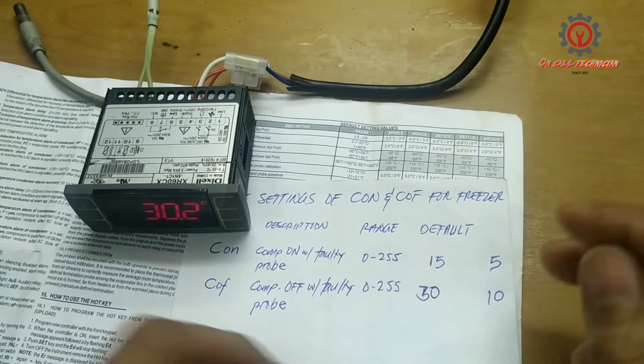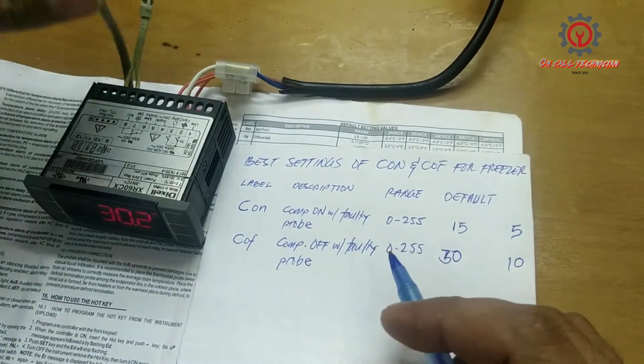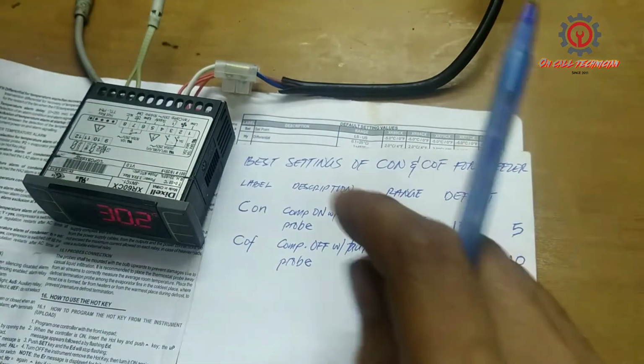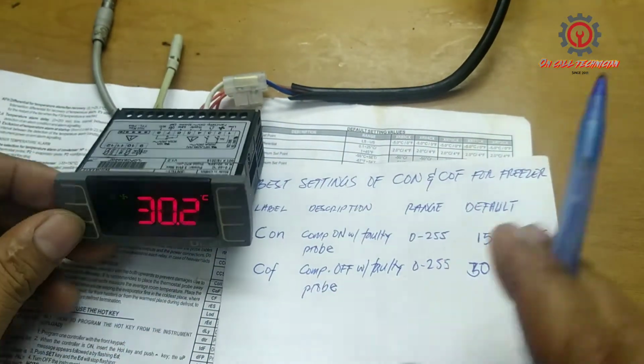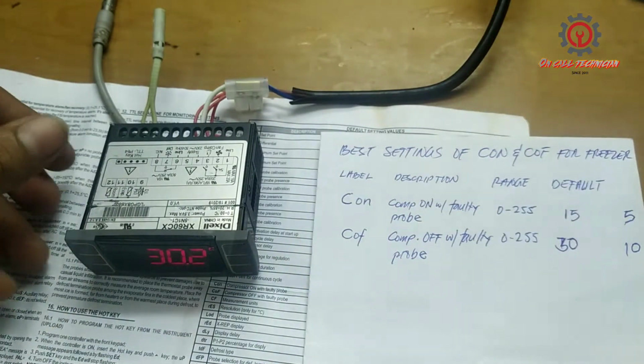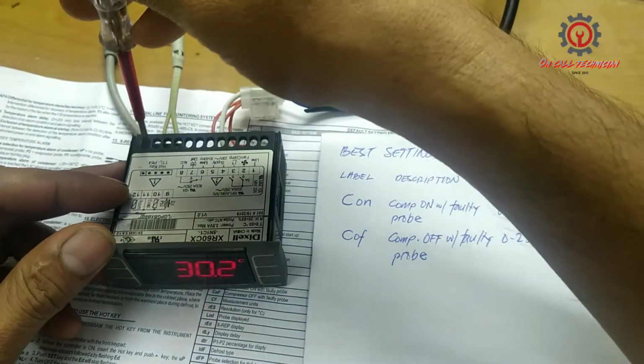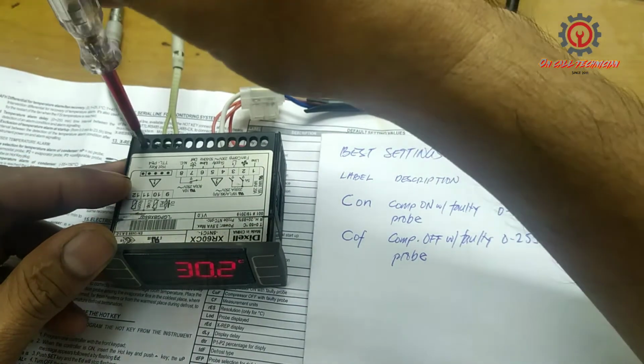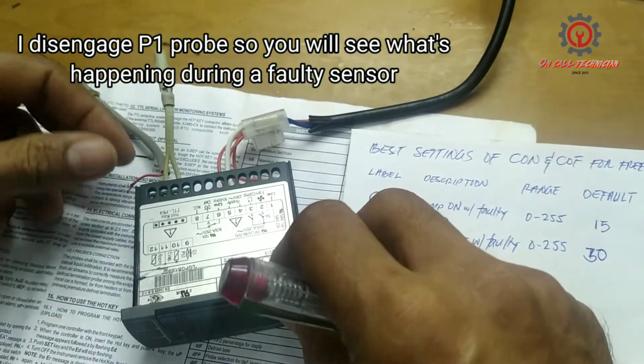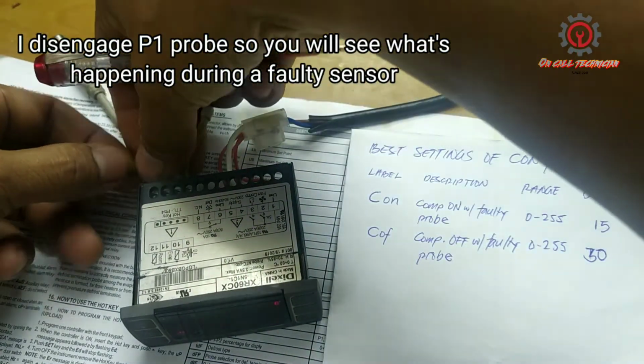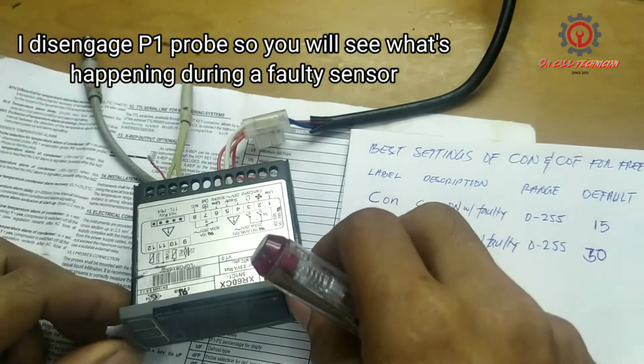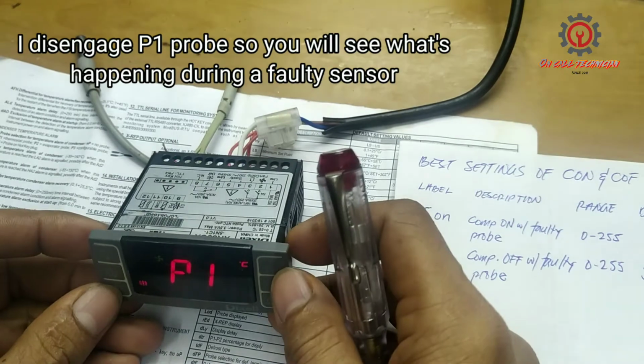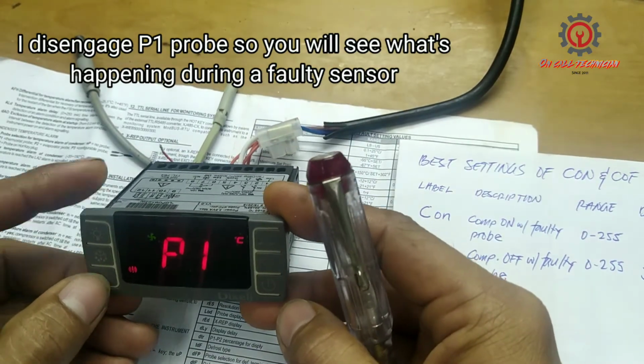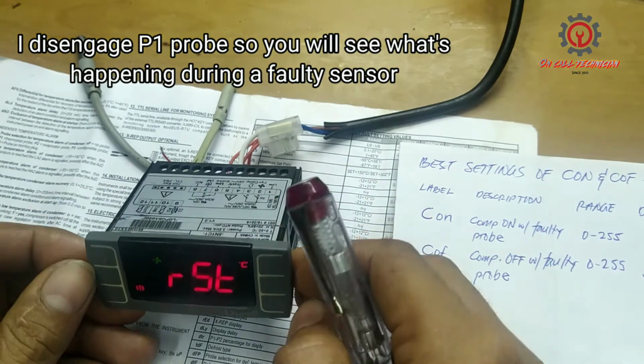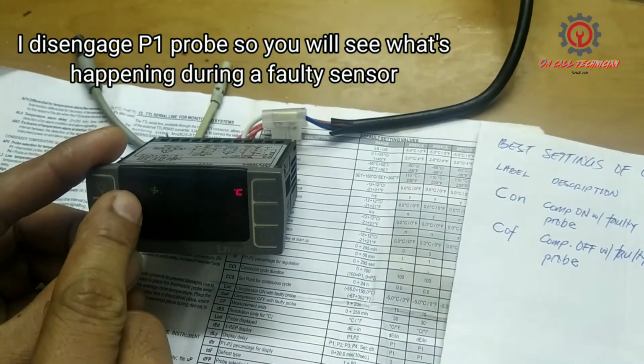And why does that happen? During the faulty probe, if this one has a problem, the P1 alarm shows up here. I'm gonna show you that the P1 alarm will engage, and I'm going to disengage this room sensor. Now we got a P1 alarm. I'm going to silent this one. As you notice, guys, the compressor is off.